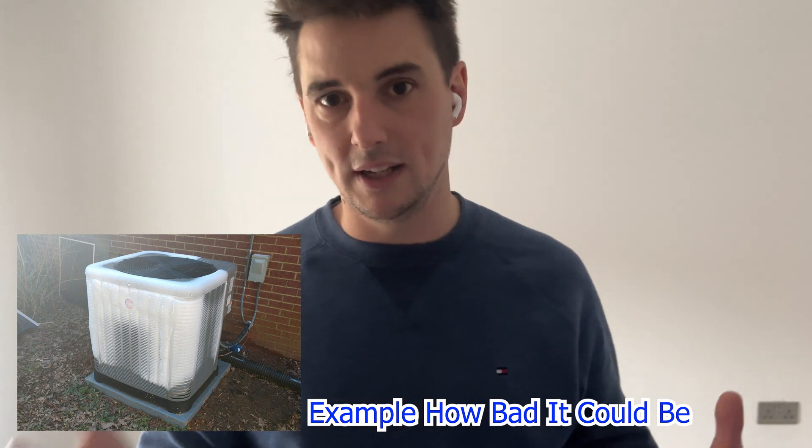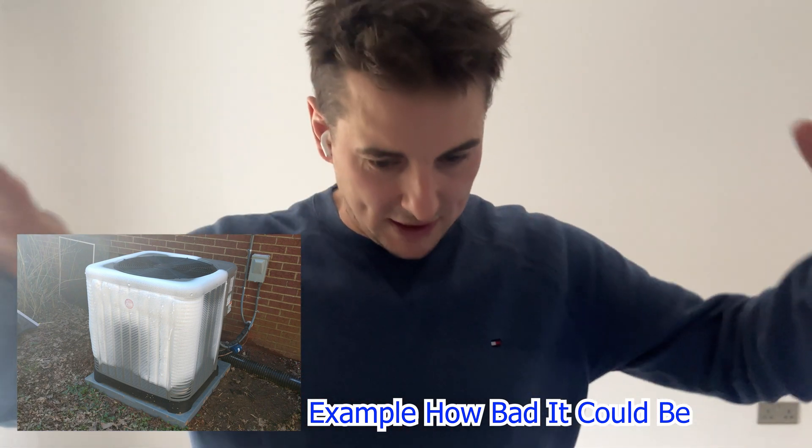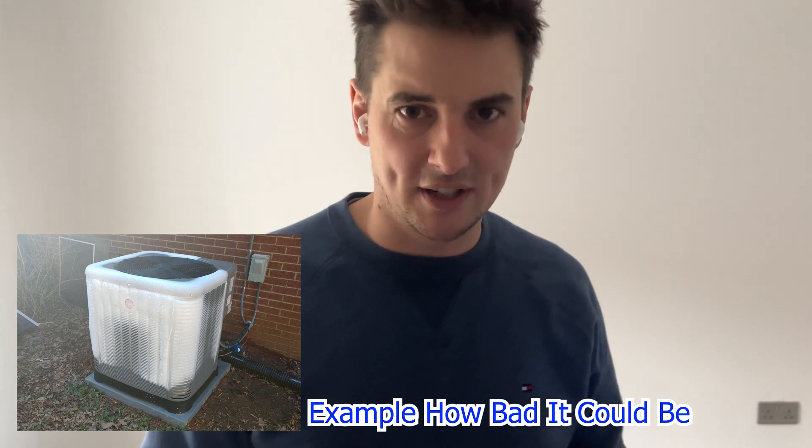From the video you can see we're not talking a massively iced-up unit — not a horror-show completely covered in ice with the blades unable to spin. It's just freezing up, working so hard that it needs to thaw out. The thawing process works fine — when it hits a thin crisp frost it shuts off, defrosts, clears completely. That element works. But it goes into that mode all the time.